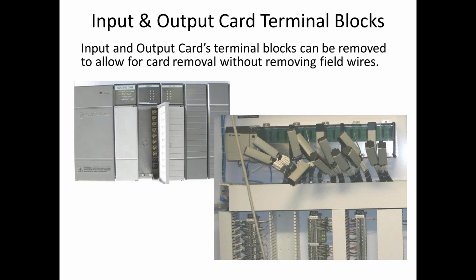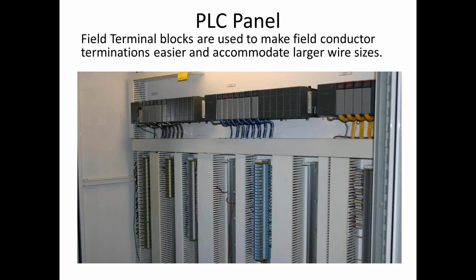So the ideal situation is to have a set of terminal blocks, field terminal blocks. They use those to make the conductor terminations easier. We can have the instrument techs take the wires from the cards and run those down to the terminal blocks, and they can take their time. They get nice, neat installations, so that when the contractor or whoever is putting the instrument in, they can just wire up to the terminal blocks. That makes the connections easier, and it also can accommodate some of the larger wire sizes.